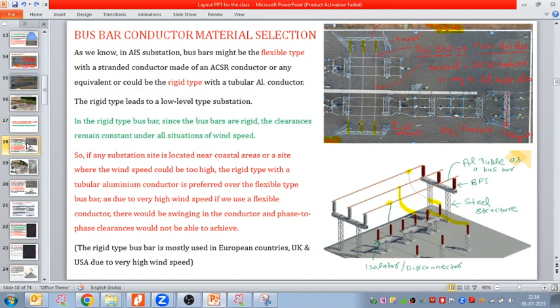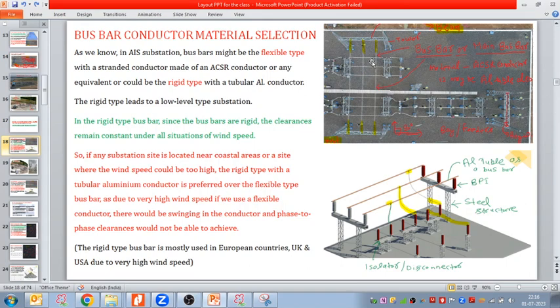With the side photo, I'll try to compare the two. This view is for the flexible busbar, and this other one is the rigid busbar, where to make the rigid busbar we are using an aluminum tube as the busbar, and that aluminum tube we place on the post insulator, and that post insulator we give support with the help of this support structure. So we are going to discuss this installation, how high from the ground, plus whether we should go with the flexible or the rigid type. As we know, in an AIS substation, the busbar might be the flexible type with a stranded conductor made of an ACSR conductor or any equivalent.